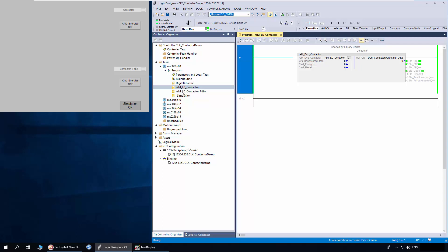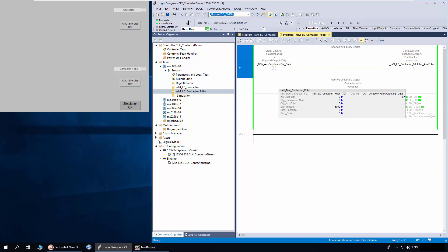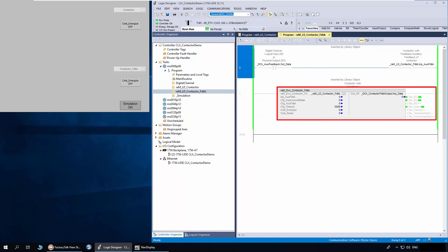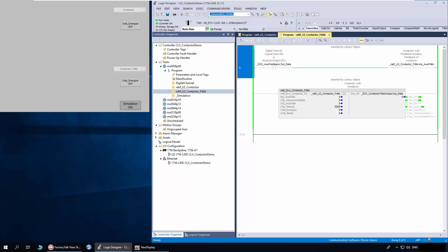I will open the contactor feedback routine. The contactor feedback object is used for a contactor with auxiliary feedback. The config aux feedback is to set the feedback polarity as normally open or normally closed. Config timeout is to set the time for the timeout error for auxiliary feedback.